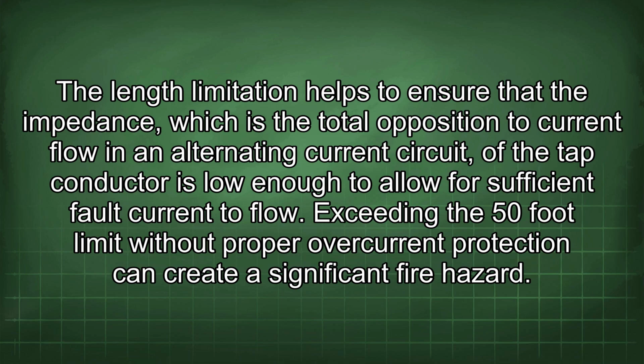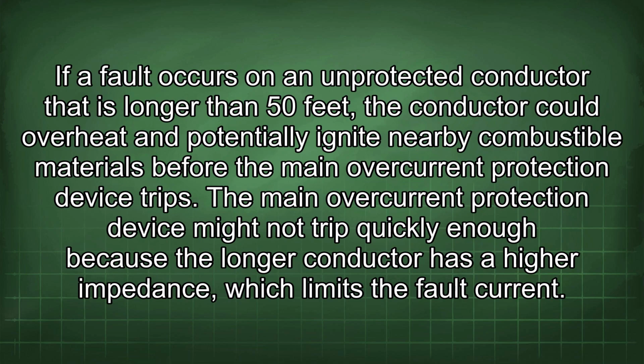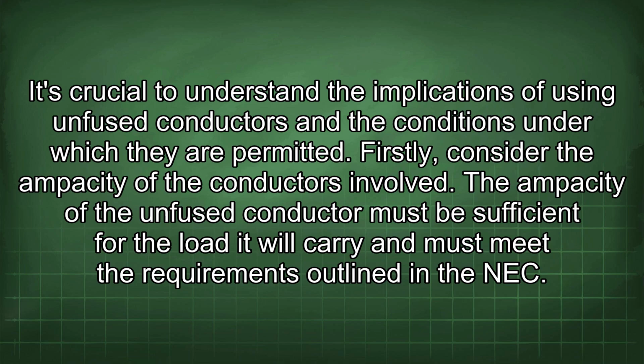Exceeding the 50-foot limit without proper overcurrent protection can create a significant fire hazard. If a fault occurs on an unprotected conductor that is longer than 50 feet, the conductor could overheat and potentially ignite nearby combustible materials before the main overcurrent protection device trips. The main overcurrent protection device might not trip quickly enough because the longer conductor has a high impedance, which limits the fault current.